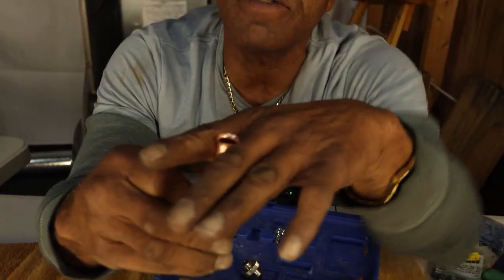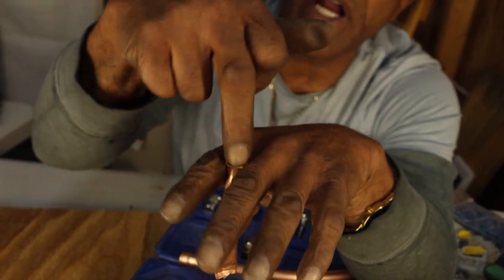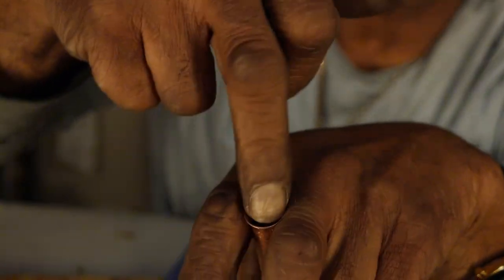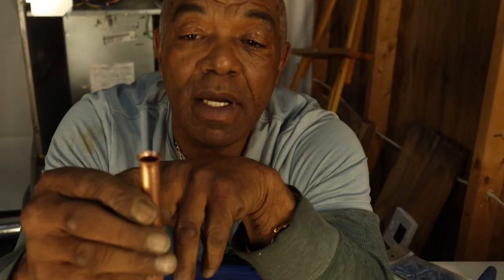Another form, and I don't have a flare nut here with me tonight, but I'll show you one. We flare this, it gets a nut outside of it, and then another nut that's beveled that fits right in that seam, and when you tighten it up with those channel locks that I was showing you earlier, it will seal and give a permanent connection that will never leak, and it'll last for the life of the system. There's a couple other ways that we connect our copper, but I'm going to show you all of them.